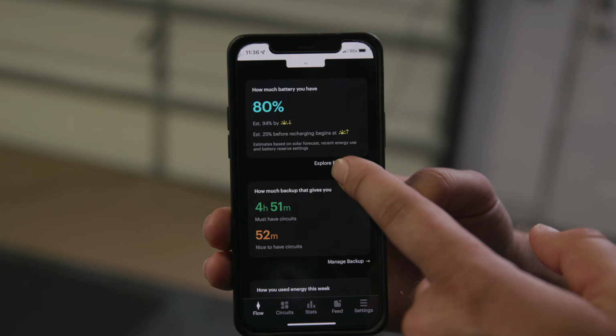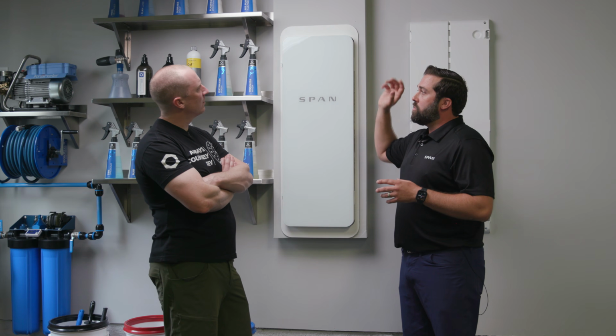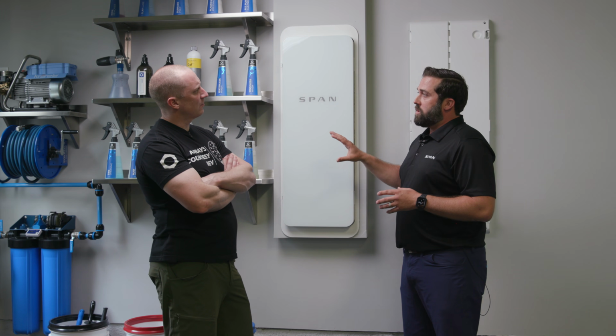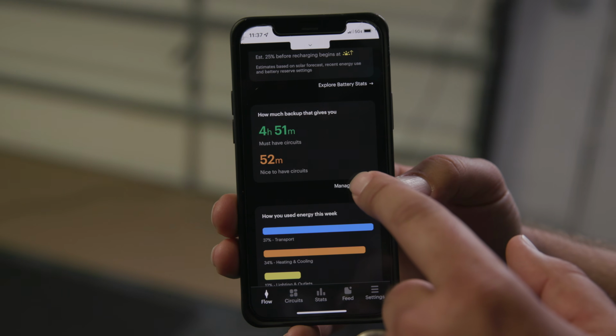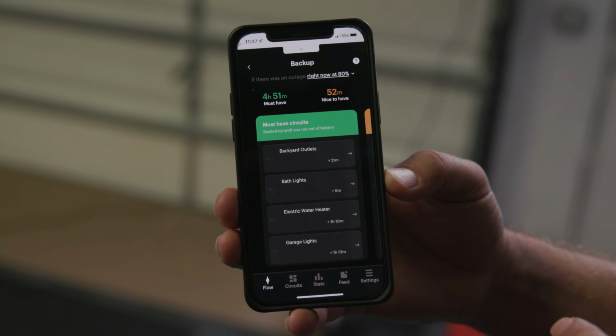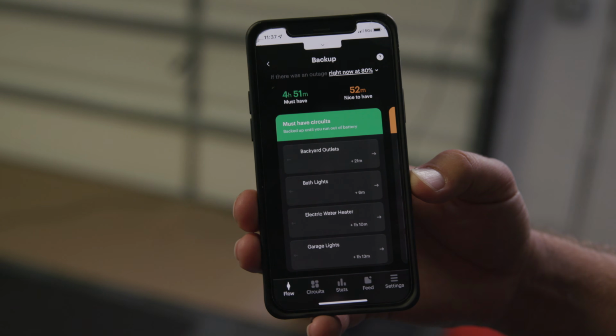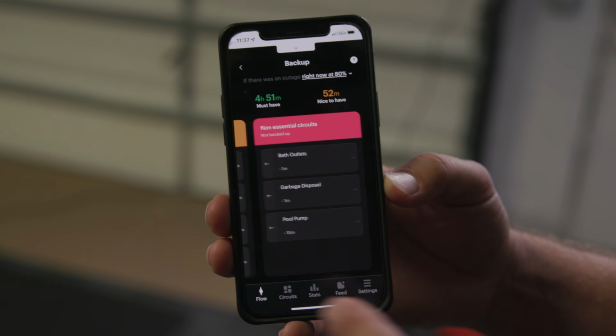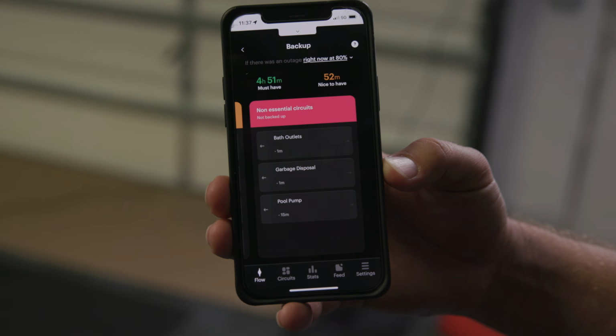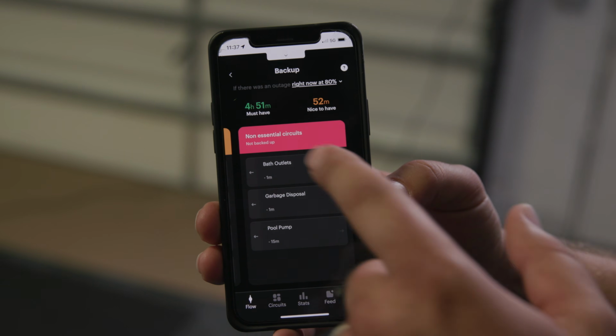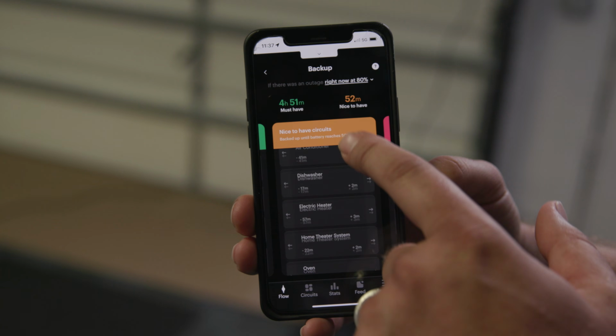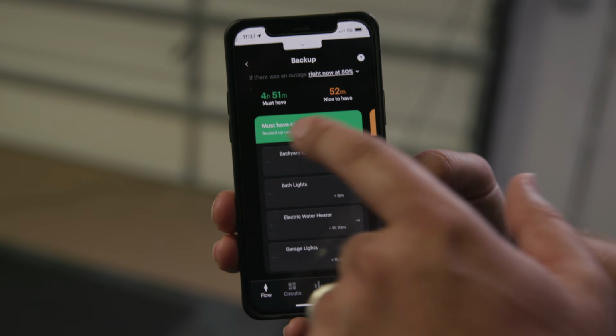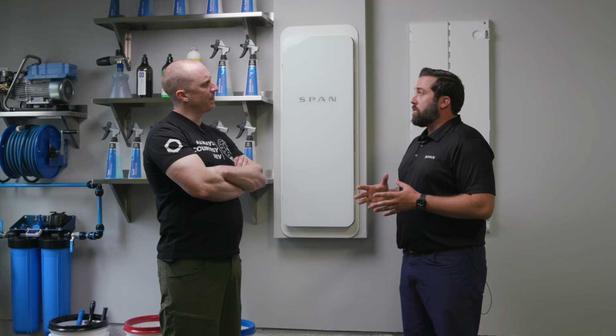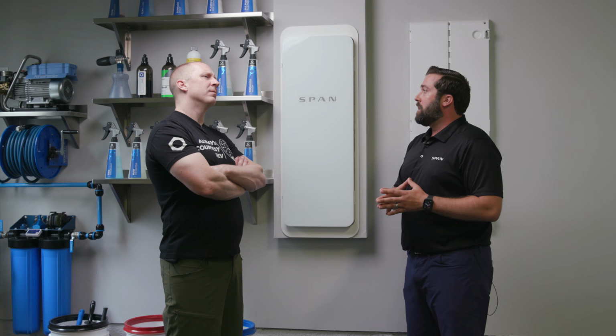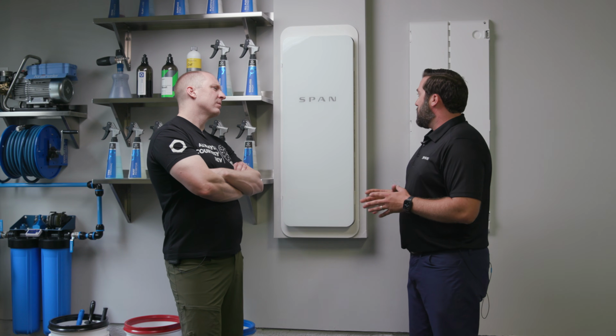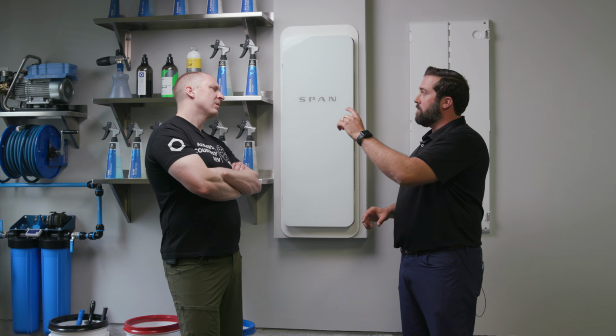The unique thing with Span is automatic load shedding. Say you have solar and Tesla batteries, the installer works with you to bucket all your circuits into must-have, nice-to-have, or non-essential. When you go off-grid, the battery kicks on, Span recognizes the off-grid event, and all the circuits you bucketed as not needed automatically shed. Your nice-to-have loads turn off automatically when the battery hits 50%, so you're only running your must-have loads. This eliminates the need for a critical loads panel with solar and storage installs, with a lot of unique features built around your must-have loads.